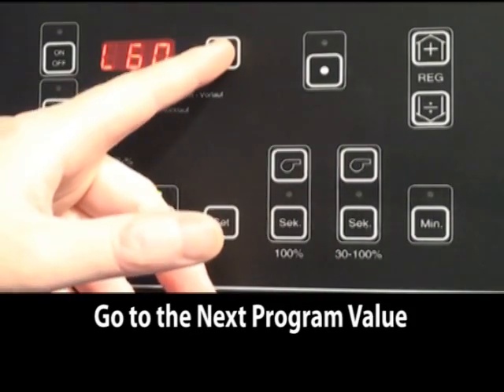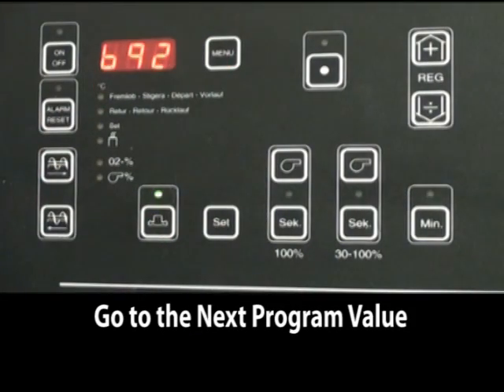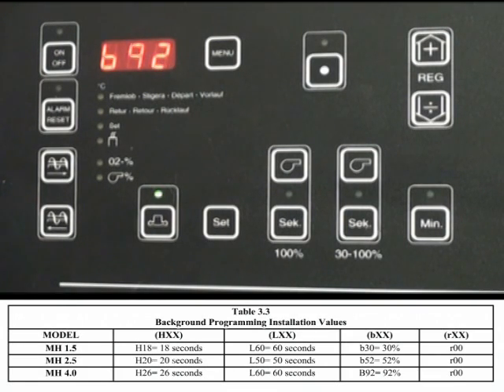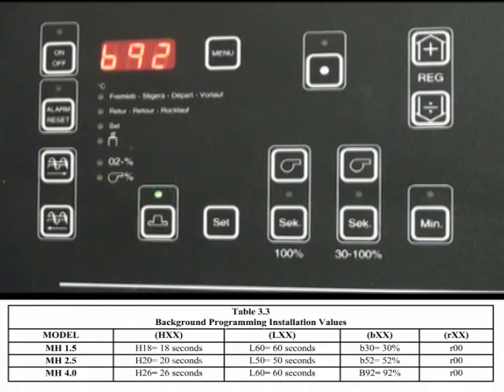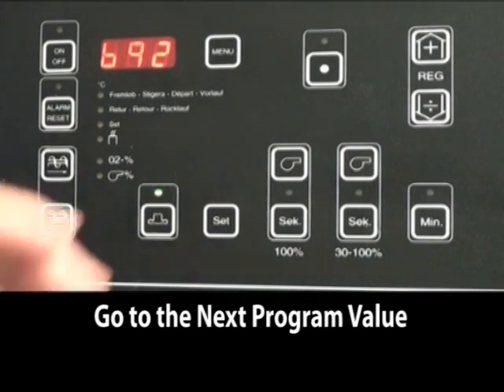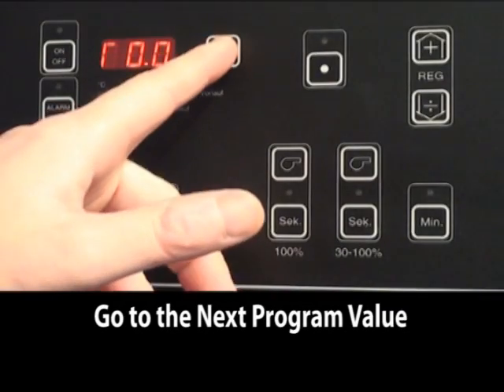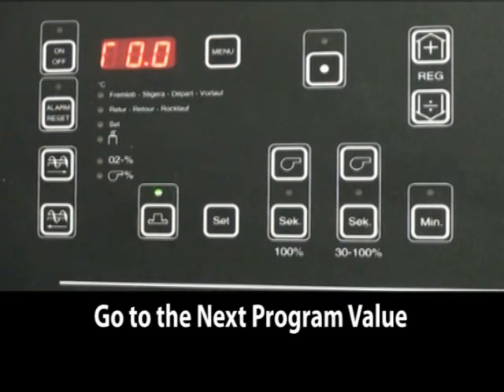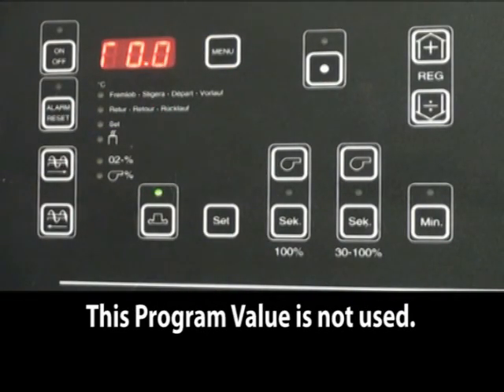The next setting is maximum allowed fan intensity. This should be either 30, 52, or 92 percent. The last setting is not used in North America, so this should not be used.